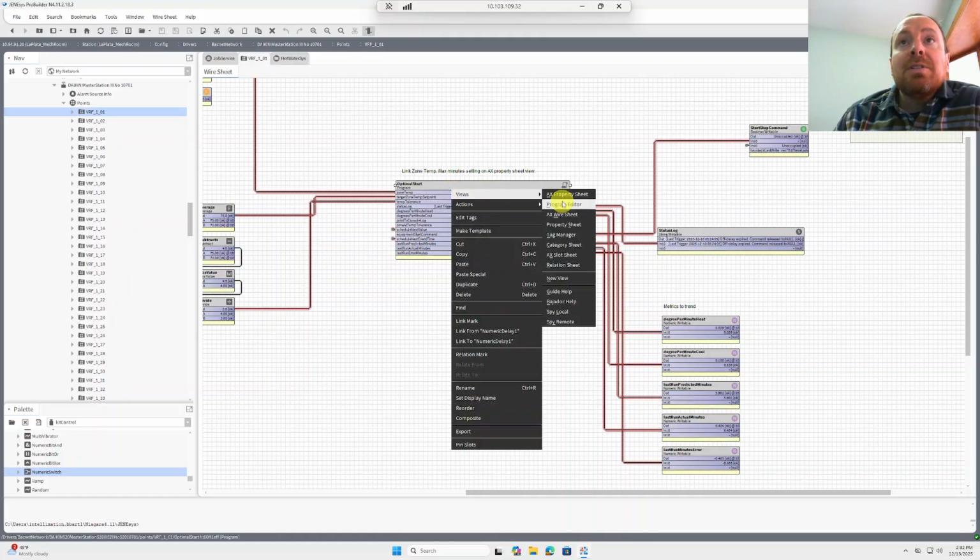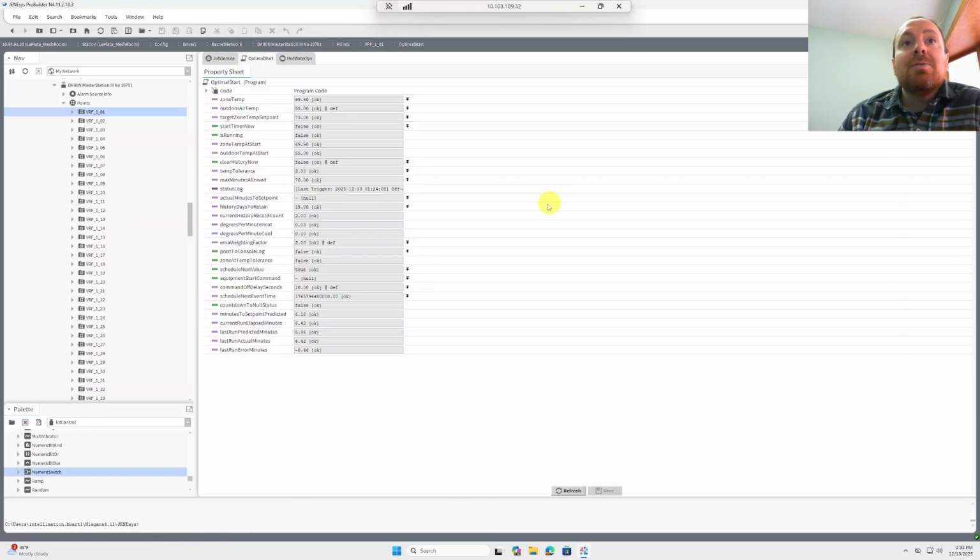And at the moment, inside these blocks, you can always go into it, even though the schedule is not actually running right now, the model is always predicting. So it's predicting 6.16 minutes of runtime based on this temperature being off from set point. So it's kind of cool. Maybe we'll get into this a little bit more, but thought I'd show you guys a little bit about that.